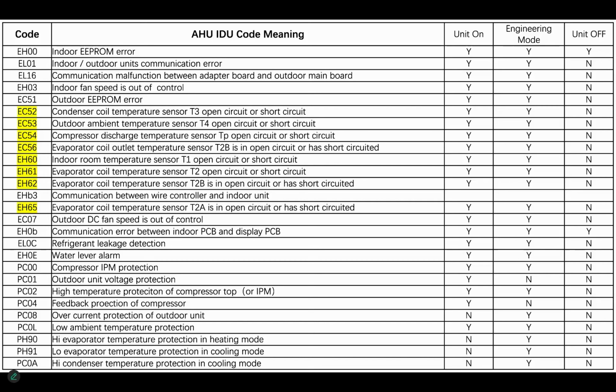What are these good sensors supposed to read? All of our sensors are 10K type 2 thermistors, with the exception of the TP sensor, which is compressor discharge. That one is a 55K, because it runs at a higher temp. It's actually 10K at a certain temperature, and I can't remember it off the top of my head, but I know it's not 77 degrees. What I can tell you is it's really close, just about spot on, 55K at 77.